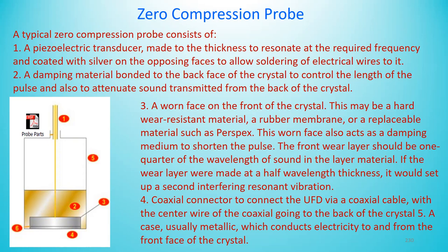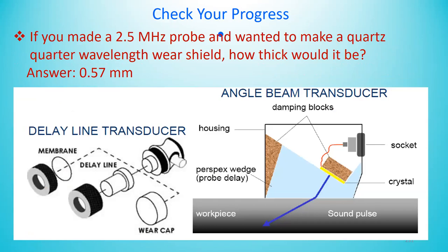Coaxial connectors connect the UFD via coaxial cable, with the center wire of the coaxial going to the back of the crystal. A case, usually metallic, conducts electricity to and from the front face of the crystal. Delay line transducer.